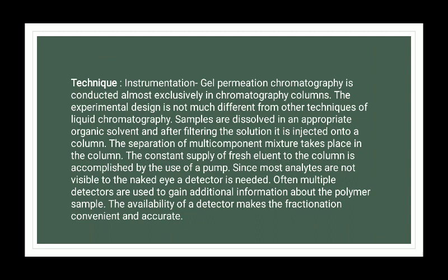Instrumentation of gel permeation chromatography is conducted almost exclusively in a chromatography column. The experimental design is not much different from other techniques of liquid chromatography. Samples are dissolved in an appropriate organic solvent and after filtering, the solution is injected onto a column. The separation of the multi-component mixture takes place in the column. The constant supply of fresh eluent to the column is accomplished by the use of a pump.